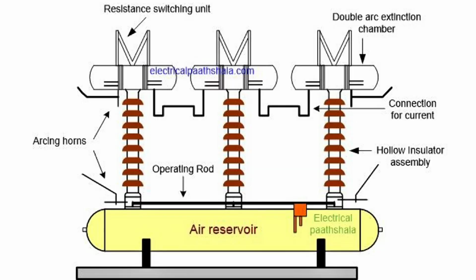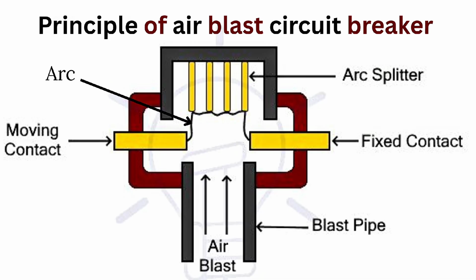The working principle of air blast circuit breakers, ABCBs, is based on the use of compressed air to extinguish electrical arcs that form when interrupting electrical fault current in a circuit. When a fault occurs, the protective relay detects the fault in the electrical circuit. The relay sends a trip signal to the air blast circuit breaker, which causes the contacts to separate. An arc is initiated due to the ionization of the air gap. The arc is sustained by the flow of current through the ionized air.